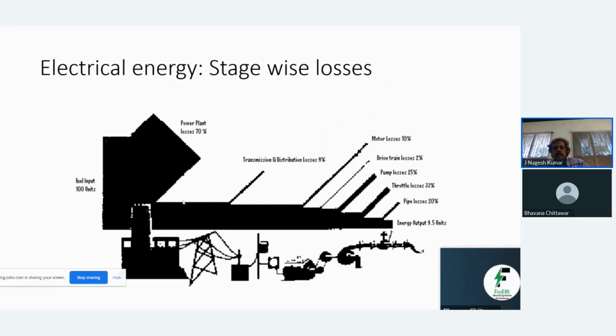So 30% electricity comes out, then it travels through the wires. T&D losses are 9%. Then it comes to your transformer in your factory, which is quite efficient, 99%. Then the motor, with an efficiency of 90%, so you lose about 10% in the motor.